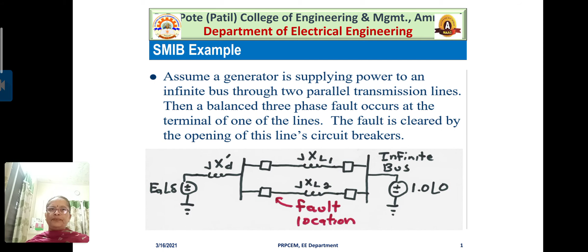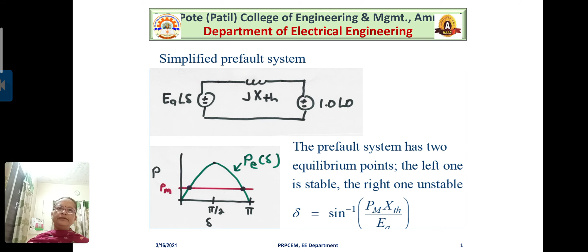So what will be the simplified pre-fault system as shown here? And it can also be understood from the power angle curve. Pre-fault system, one can say that is a good system. Everything is okay. Healthy system. The pre-fault system has two equilibrium points. The left one is stable and the right one is unstable. You can see here. And you can also calculate it, that is sine inverse of PM XTH upon EG here. XTH is the total equivalent reactance of the system, because we consider here parallel transmission lines. So you have to find out XTH, meaning X equivalent, the parallel combination of two reactances. Right?